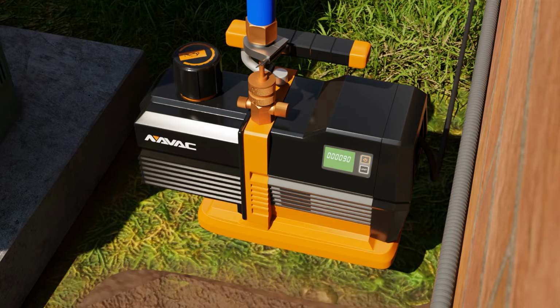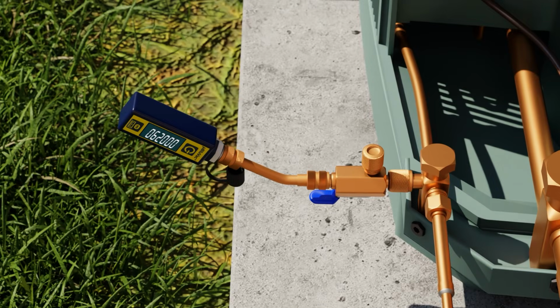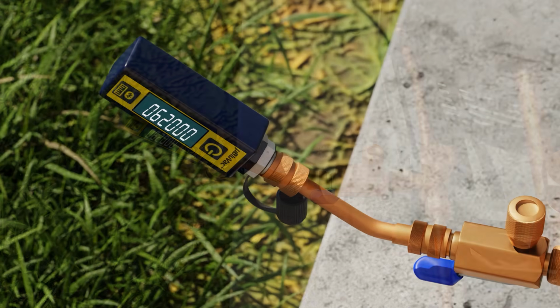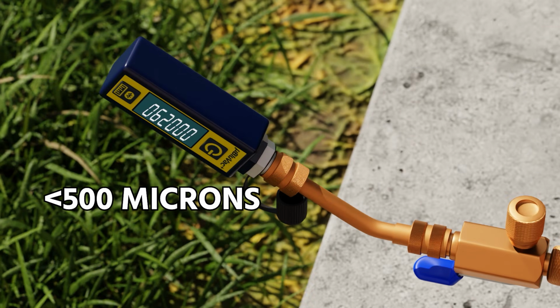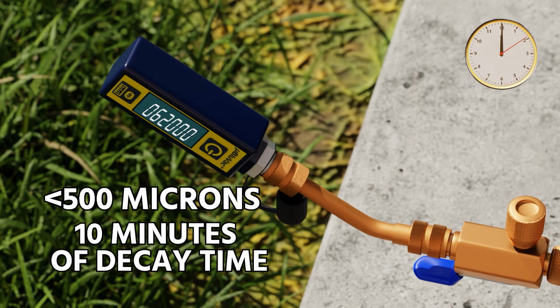Now do your isolation test by shutting off the suction valve and ensure that the vacuum doesn't decay significantly. Decay in this case just means that the micron level rises rapidly. Generally speaking, you don't want it to go above 500 microns in 10 minutes of decay time if you pull down below 300. On a typical residential system, staying below 500 microns in 10 minutes would adequately confirm that there aren't significant leaks and that you have a deep vacuum.